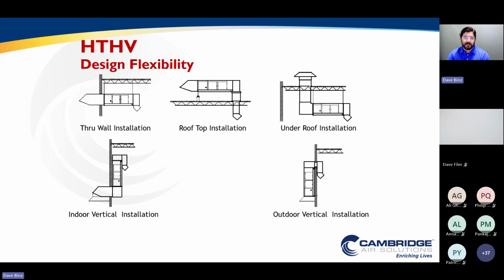Similar to the makeup air applications, these solutions can be highly flexible for where and how you install them. Again, horizontal or vertical, outdoor or indoor, roof mounted, pad mounted, or even wall hung. One of the things we often see inside of these warehouses is that typically you're going to put the equipment on the roof. Even a 2 million BTU space heater is still only going to weigh about 2,000 pounds and be the size of maybe your traditional desk or credenza, not a very big piece of equipment. So it doesn't take up a lot of space, and this equipment can be moved around the facility without having to do too much to the building structure.